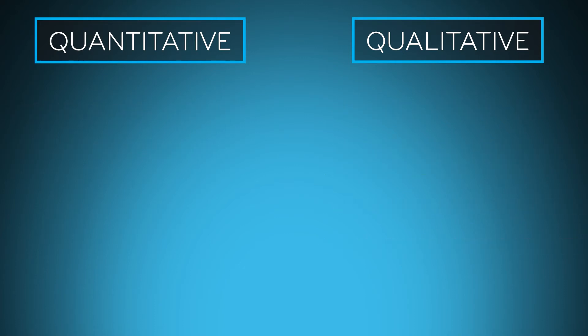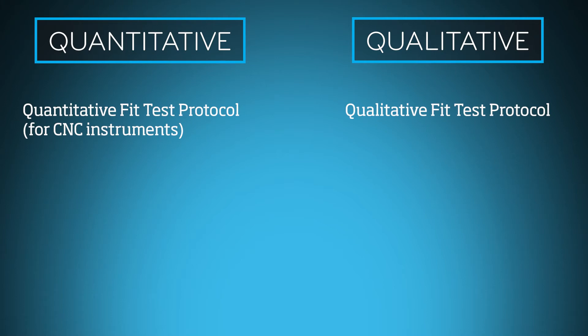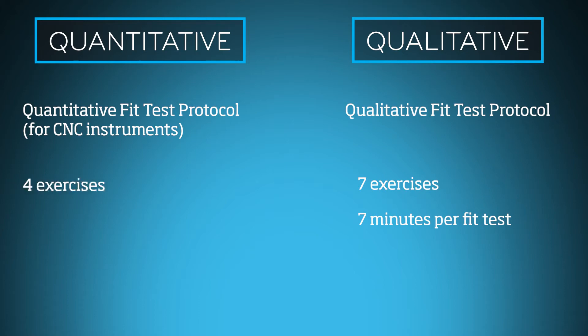The two testing methods we are comparing use different OSHA protocols. The qualitative fit testing protocol requires seven 60-second exercises, totaling seven minutes. The quantitative protocol used by PortaCount instruments requires only four exercises of varying length, totaling two minutes and 29 seconds.